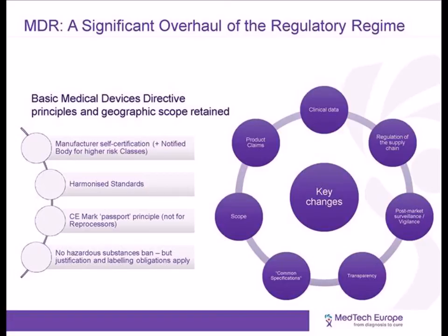A key feature of the new regulation is continued use of CE marking, or the CE marking passport principle. This principle is maintained under the new regulation, meaning that lower risk devices can be self-certified by the manufacturer. But for higher risk devices, we have oversight by notified bodies, which are third-party certification bodies. For CE marking purposes, manufacturers can continue to use harmonized standards as a key but voluntary compliance mechanism. And while EU regulation of medical devices remains based on CE marking under the MDR, the new regime is expected to be enforced and overseen more stringently and consistently than the previous directives.